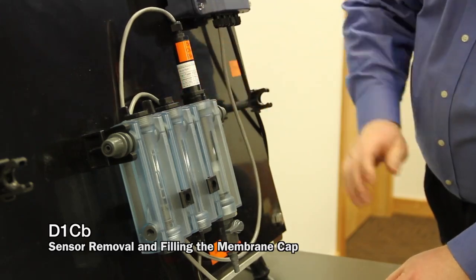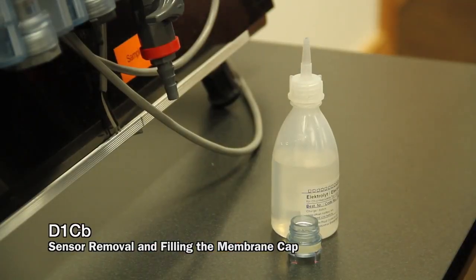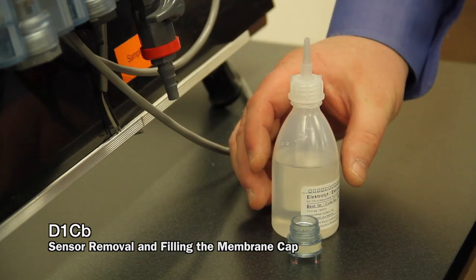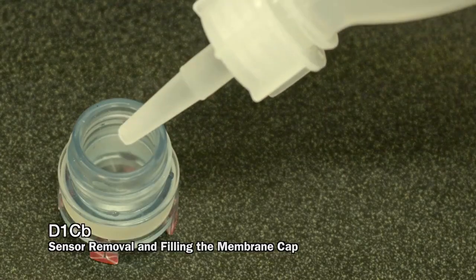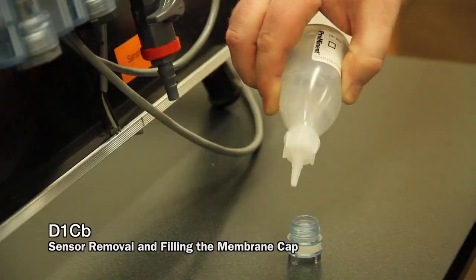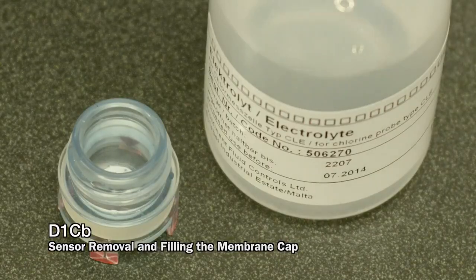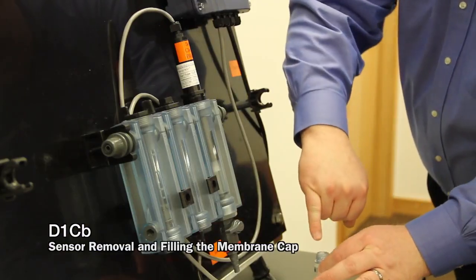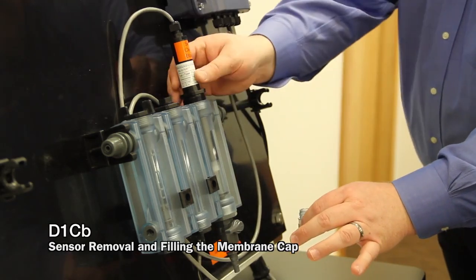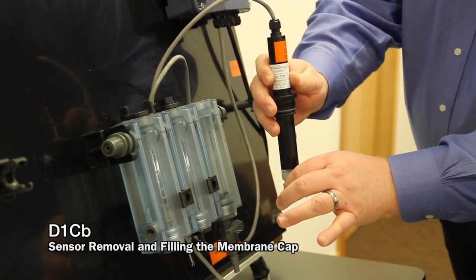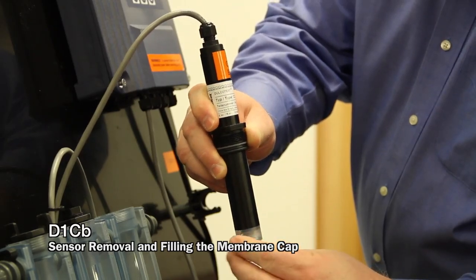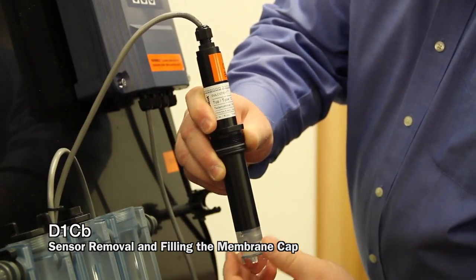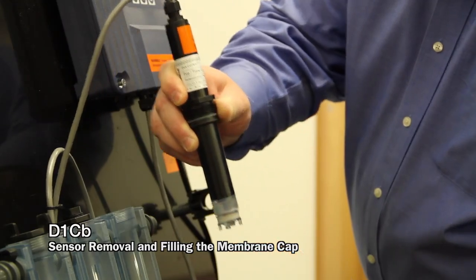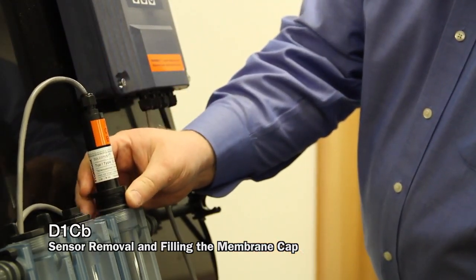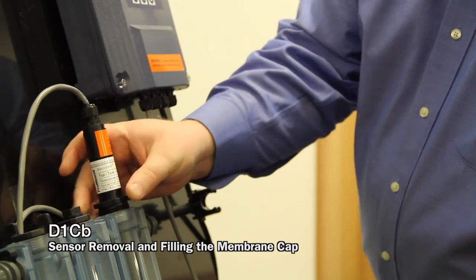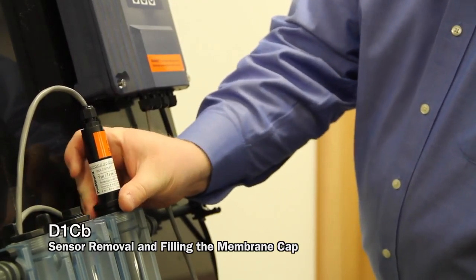I'm just going to place that there for the time being. Now this particular sensor has a very water-like electrolyte. We're going to fill that cap full. Be sure that there are no air bubbles down where the membrane is inside of the cap. Thread that cap back onto the sensor. Place the sensor back into its sample cell and tighten our compression fitting back in place.